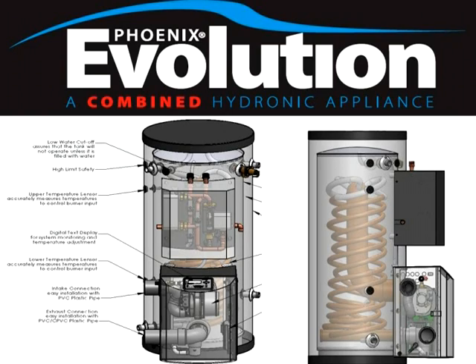You'll see here is a control. That's the integrated control that is controlling both the space heating and the water heating in a relatively sophisticated manner within this unit. And above here is the variable speed circulator and the plate heat exchanger. You'll also see there are unions in there. That heat exchanger can very easily be detached, put in a bowl of muriatic acid or some other kind of cleaning fluid, and be cleaned if ever that's needed in a particularly nasty water condition.